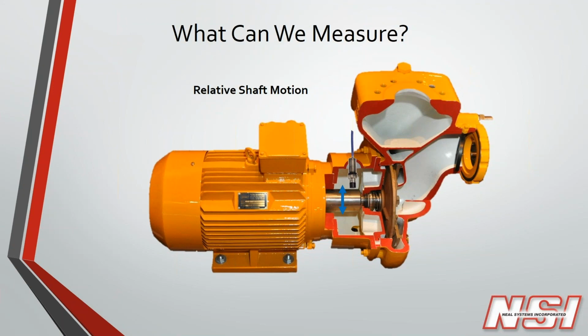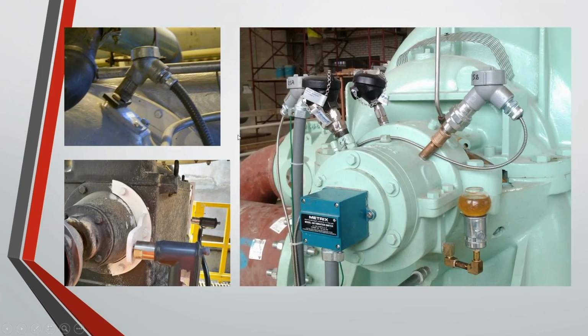So I'll show you some examples of sensors mounted. Up here in the upper left side, I've got a pretty typical installation for a retrofit of a velocity transmitter. The velocity transmitter is right here, and then you've got your conduit elbow to connect to it. That velocity transmitter is mounted on a little mounting pad that is bolted on securely to the machine housing. I say this is a retrofit because it looks like the manufacturer of the asset did not include a specific mounting for this device, and so they needed that pad. And this looks like it's going to work pretty well. That would be considered a pretty good mounting for an instrument like that.